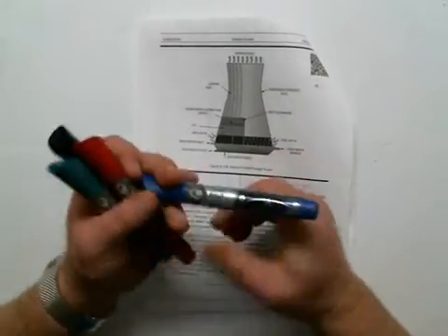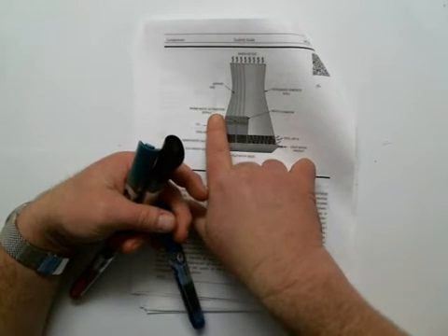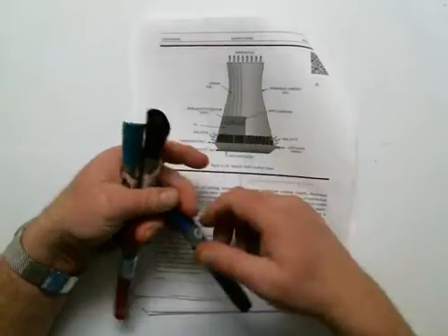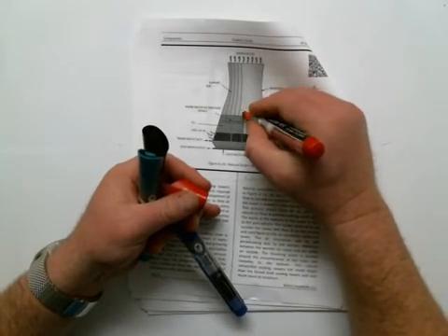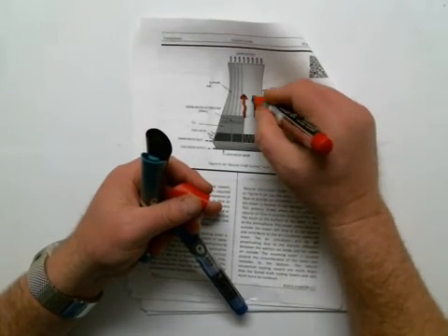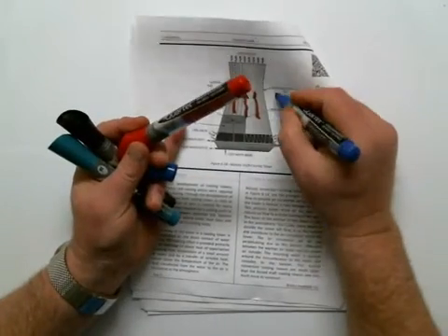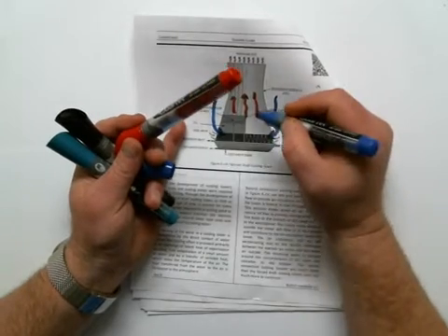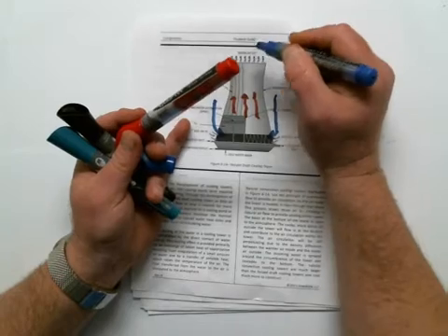And the hot circulating water will actually be injected into this cooling tower with a warm water distribution header up here, and it'll spray downward. And this is an air-to-water heat exchange. So the hot air will tend to rise up, so it's less dense. And the colder air out here is falling, and it's going to be going in this direction. And the hot, moist air with some steam is going to actually come out the top.